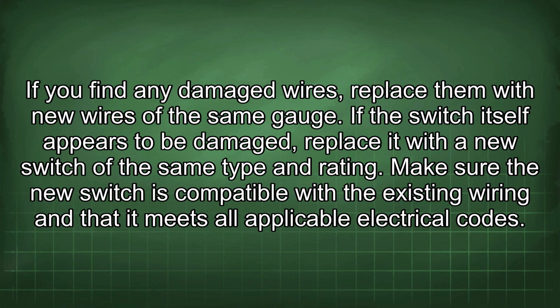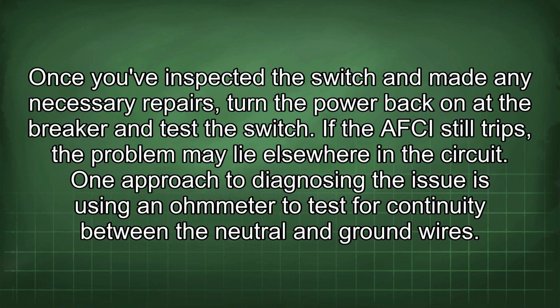If you find any damaged wires, replace them with new wires of the same gauge. If the switch itself appears to be damaged, replace it with a new switch of the same type and rating. Make sure the new switch is compatible with the existing wiring and that it meets all applicable electrical codes. Once you've inspected the switch and made any necessary repairs, turn the power back on at the breaker and test the switch. If the AFCI still trips, the problem may lie elsewhere in the circuit.